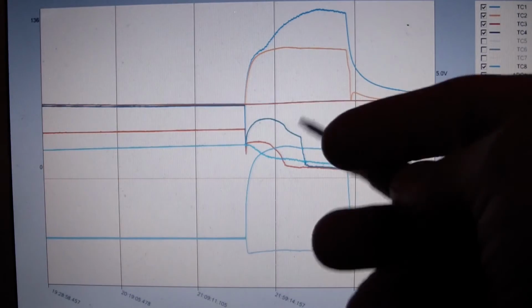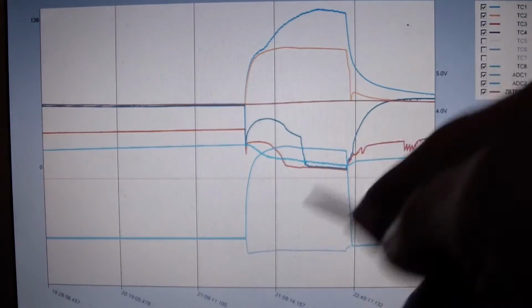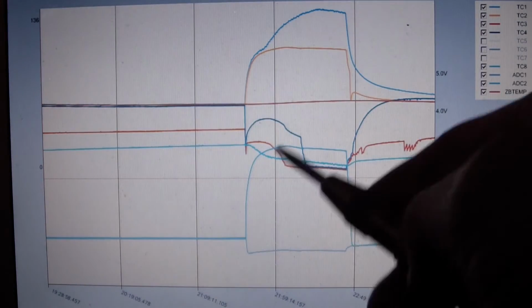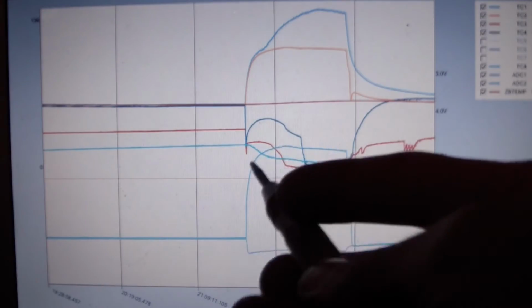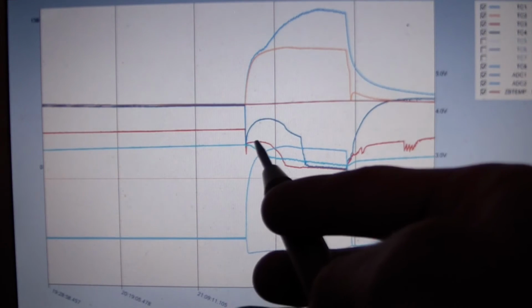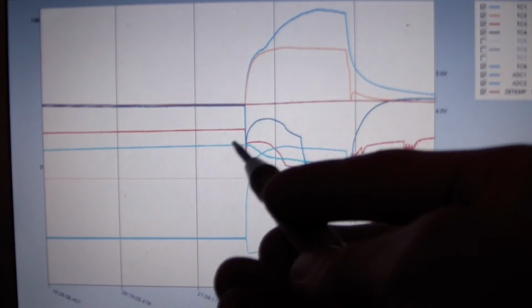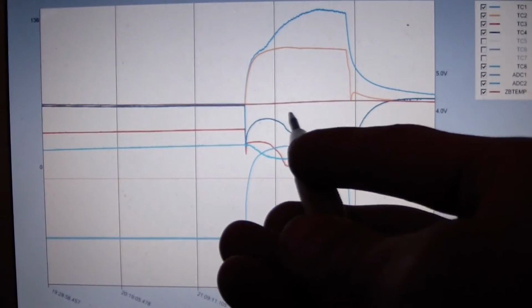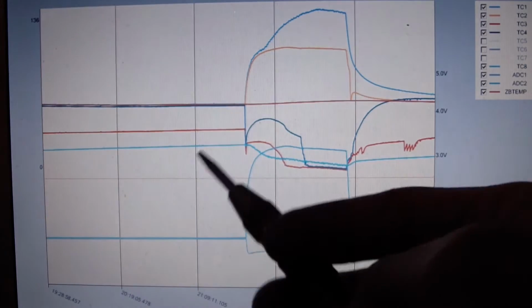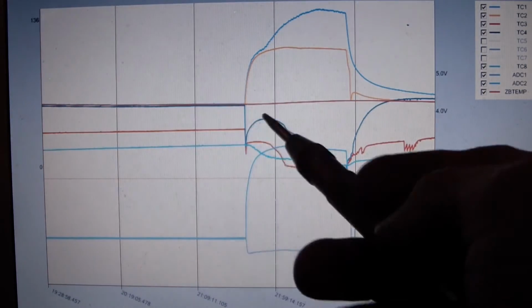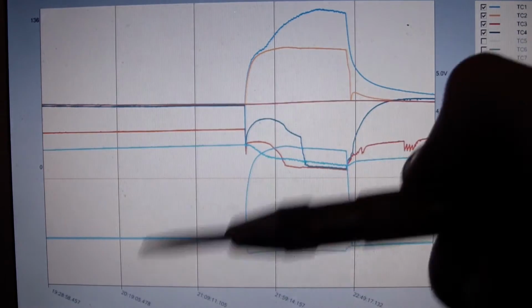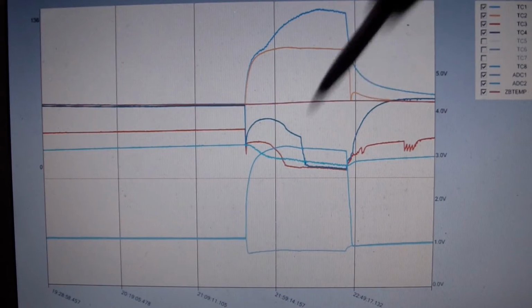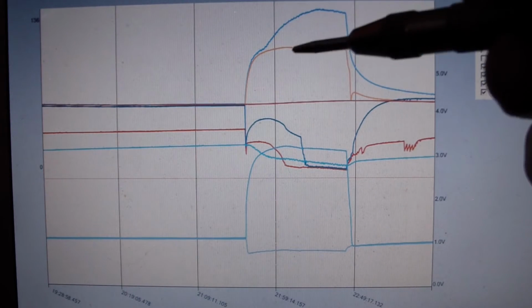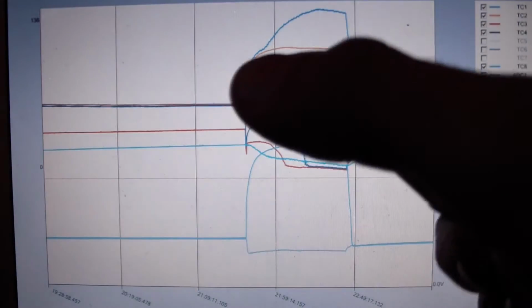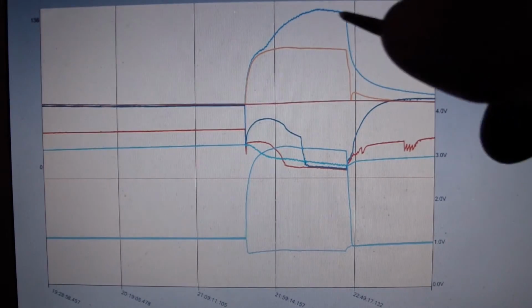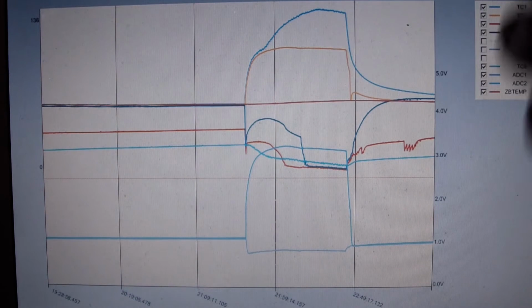In addition to that, you also have the fact that the liquid around the copper tubing is a bit warmer, and it's going to flash off a lot of that refrigerant pretty quickly. So we end up with a superheated condition in the suction line. And then, like I said, with that cap tube wrapped around with the heat interchanger, the actual gas temperature that the intake is getting on the compressor is a bit warmer because it's cooling down that warm gas that's passing through the cap tube. The other limiting factor is the cap tube itself in startup, because we're just passing gas mostly through it. We're not getting any condensation right off the bat. Cap tube doesn't really pass gas all that well, so you get this choked flow in the cap tube.